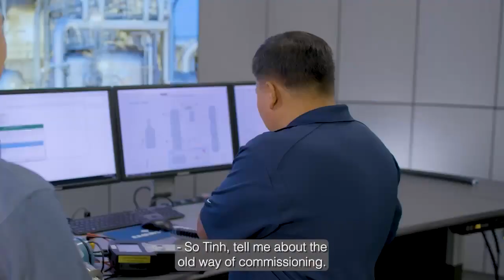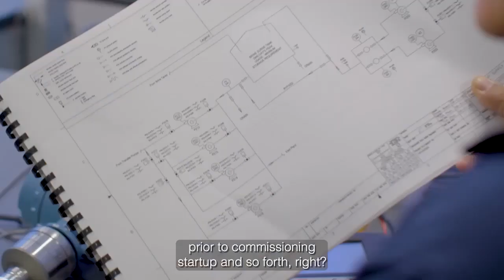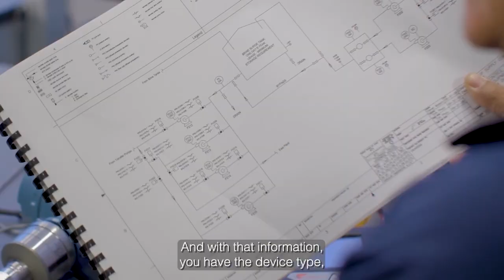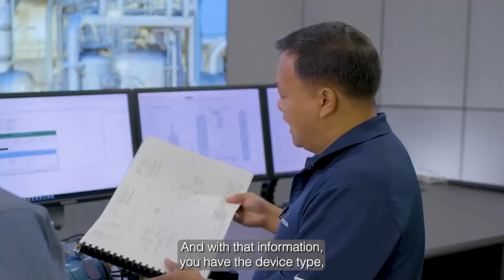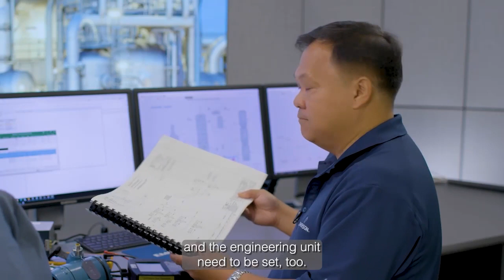So, Tin, tell me about the old way of commissioning. First of all, you've got to get the engineering drawing done prior to commissioning and startup. With that information, you have the device type, the tag name, and in the loop drawing there will be the upper range, lower range, and the engineering unit that needs to be set.